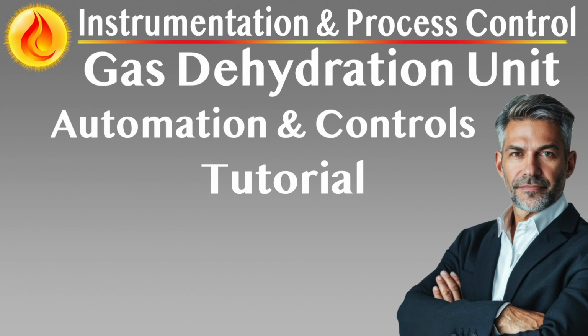High temperature trips, TS trips, and flame failure interlocks initiate burner shutdown via ESD. Flame scanner and UV detectors ensure burner integrity. Hot oil systems. Temperature control loop regulates hot oil flow through reboiler coils. Flow transmitters, FT, and control valves, FCV, manage heating energy input.